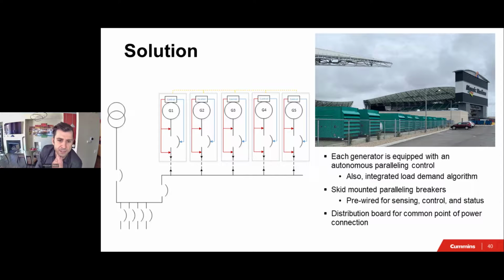So the solution here is to use, for every side of the building, 5 generators, 500 kilowatt each, and to use the integrated control, the paralleling control that I just described. They're containerized, so they're mounted outdoors with NEMA 3 enclosures. By the way, the paralleling circuit breaker was onboard, a skid-mounted paralleling breaker. The control that I described was responsible for controlling the circuit breaker, and it was pre-wired from the factory to do the sensing on the line side and the load side. There were only a few cables we needed to run for load share and first-hour arbitration from generator to generator, and obviously the power cables that go from the enclosures you see here into that point of common connection.